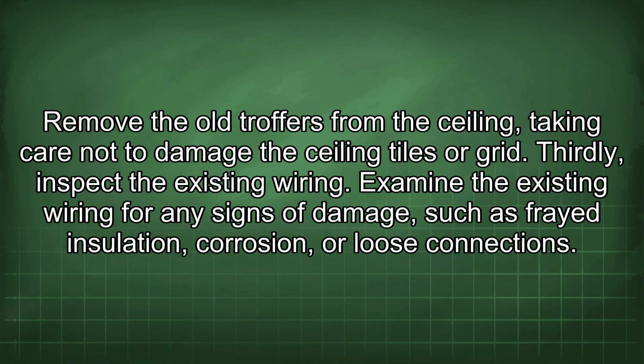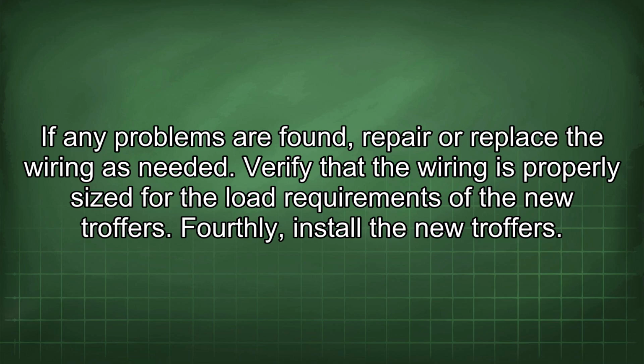Thirdly, inspect the existing wiring. Examine the existing wiring for any signs of damage, such as frayed insulation, corrosion, or loose connections. If any problems are found, repair or replace the wiring as needed. Verify that the wiring is properly sized for the load requirements of the new troffers.